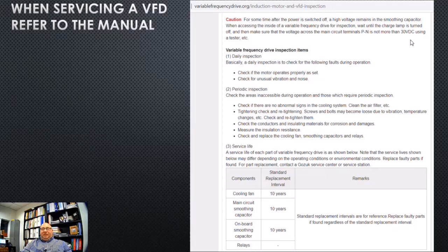Some VFD drives do not have that. And that's where we want to use our meter in DC to make sure that there's no voltage present, not only on the AC side, but on the DC side as well. And follow company policy. So when I was working on bigger VFDs, ones where the starter panels were as big as I was when you opened up the door, we used to have to wait 15-20 minutes for the DC power bus to dissipate itself and work its way out of the system. Whereas the smaller drives nowadays could be up to 30 seconds and they're fully dissipated.